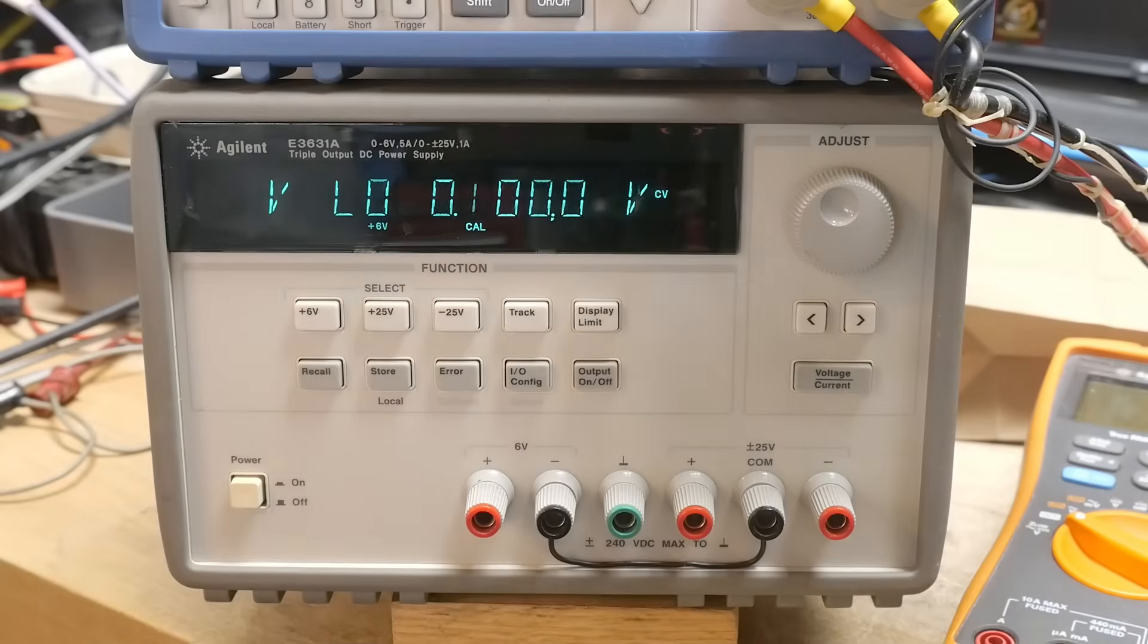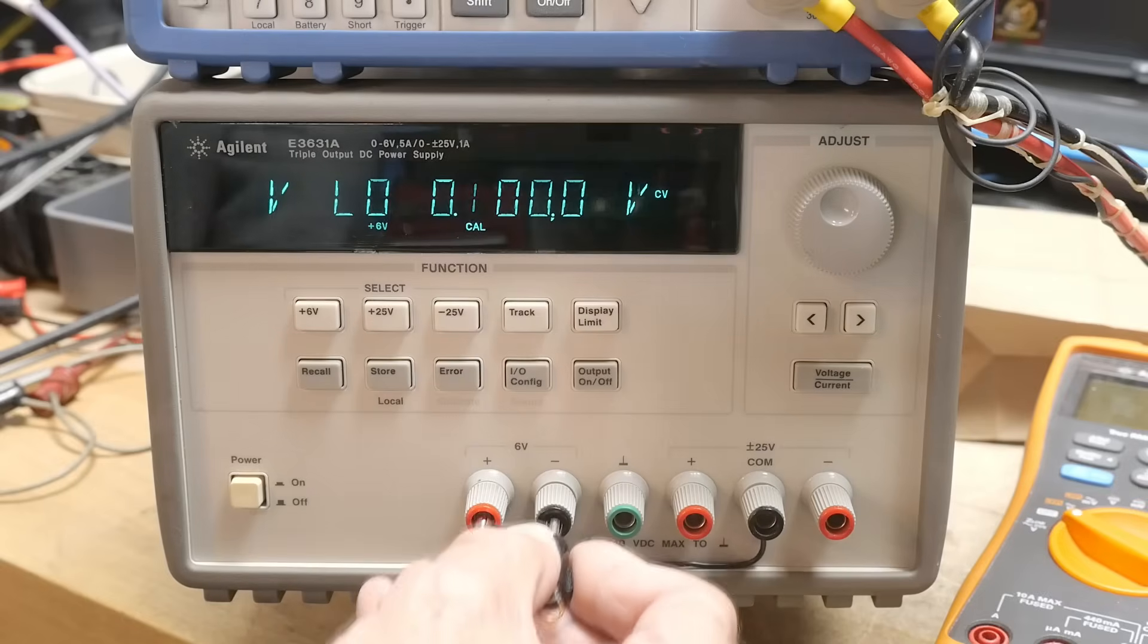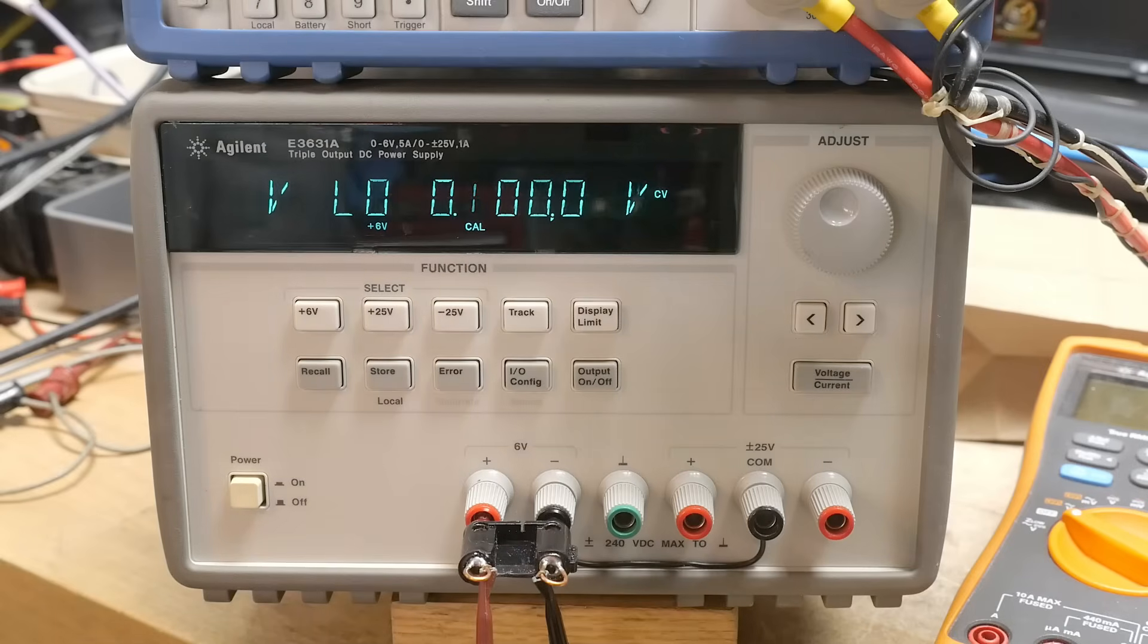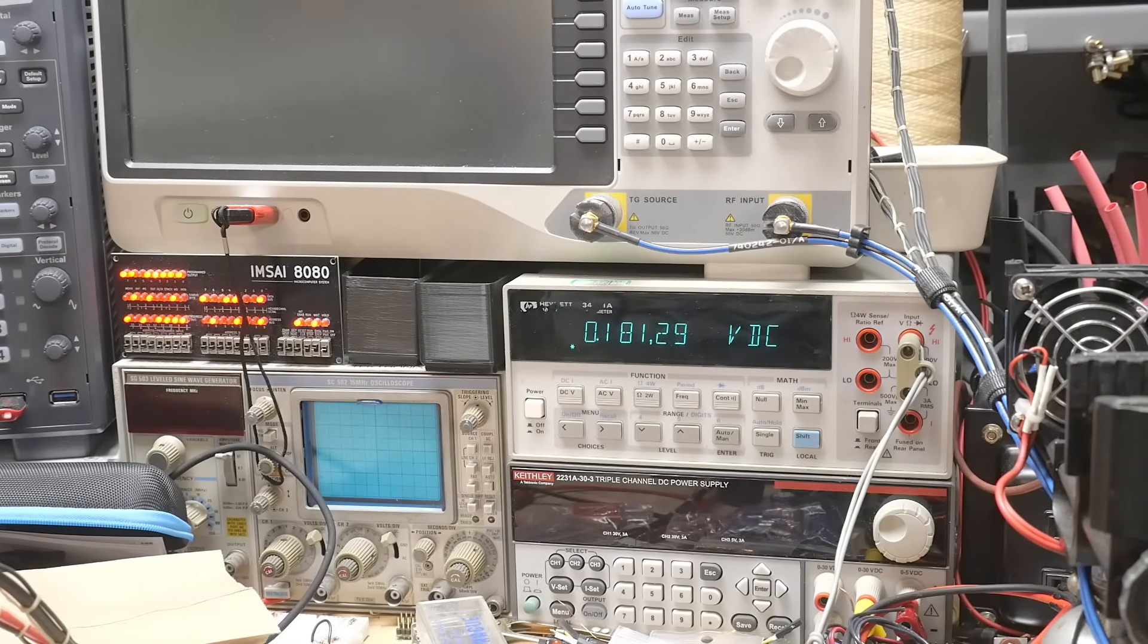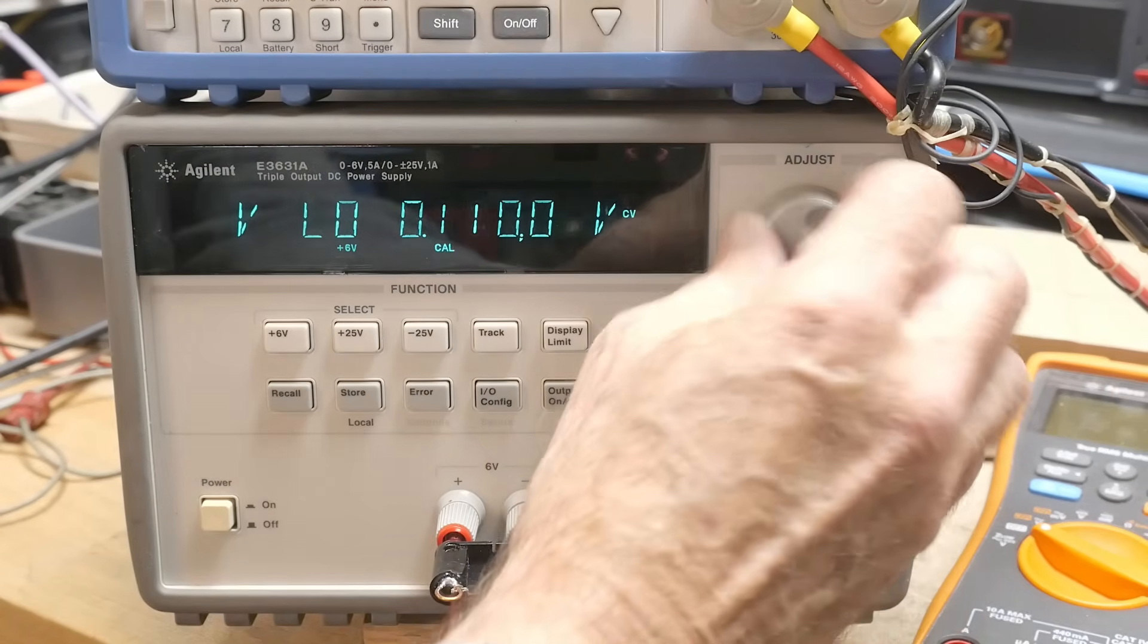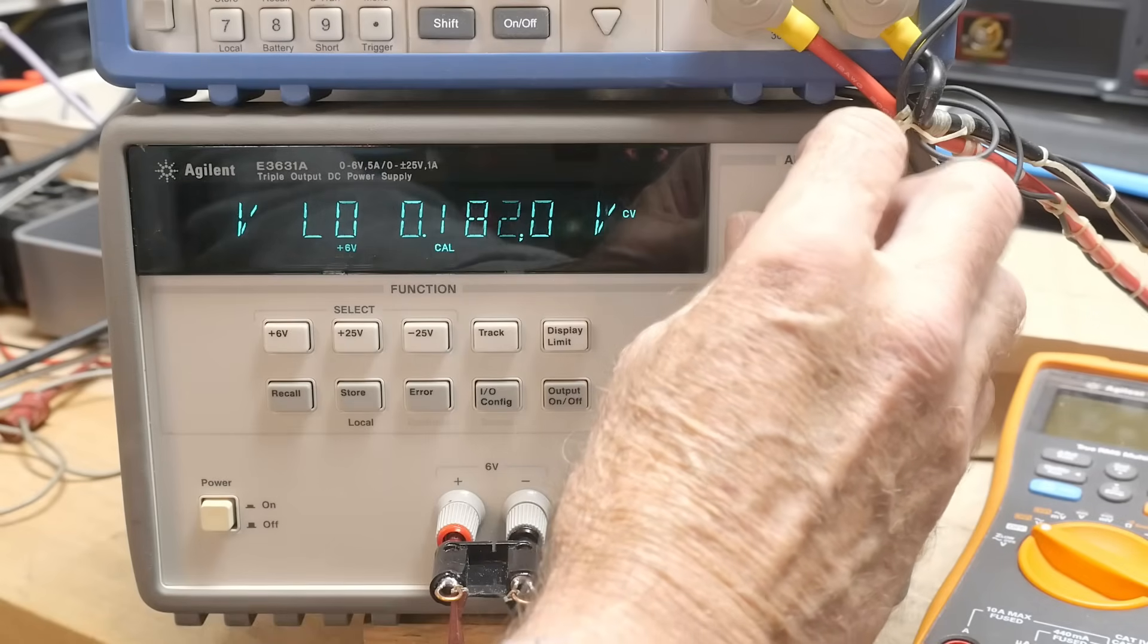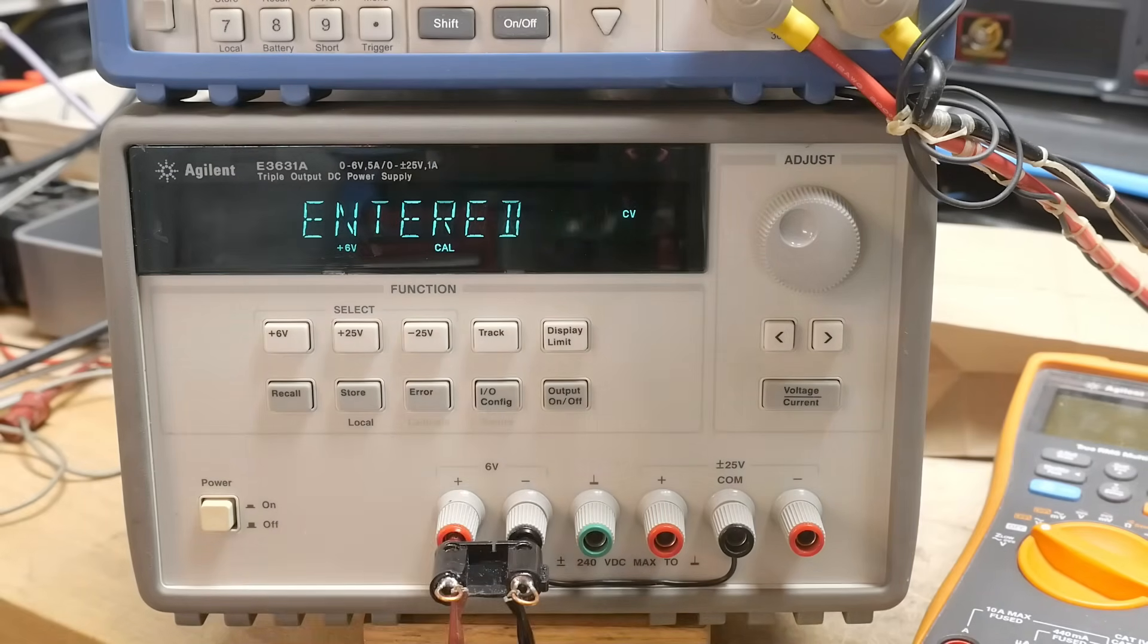And so it's outputting this right now and it wants you to check it. So this starts out on the six volt one. So we will hook up a DVM here and you go over there and you read the number you've got. So it's not the same number. It's one eight one and over here we have one zero. So we'll say okay, this is what we actually got. We'll hit calibrate.